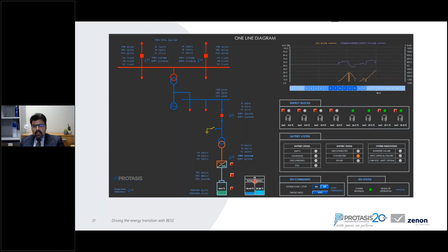In this slide, a detailed representation of the battery system is depicted. In this screen, the main characteristics of the batteries, such as the state of charge, the DC current, and DC voltage, are shown here, as well as inverter status and temperature measurements. Alarm handling is a major task for complicated systems like this. So we selected to utilize zenon Alarm Areas functionality. It is the white A buttons that you see here. This feature provides to the operator the ability to understand, localize the problem, so interact in a fast and secure way.